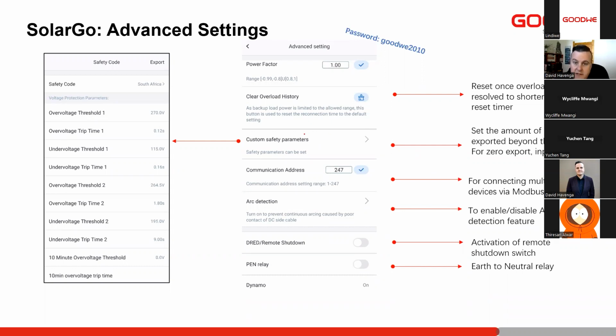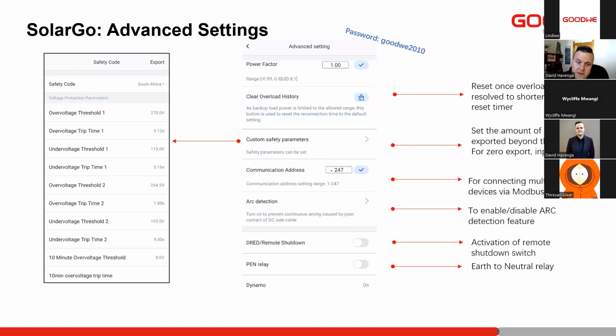Next, we have custom safety parameters. If you do select a country safety parameter, but you have special requirements, you are welcome to also adjust this. If you have a country that has very specific requirements for the inverter connection, you can adjust these values individually. Next is the communication address. The communication address is only really used when we are paralleling or connecting to EMS devices or third-party devices. Then we can change the communication address for the RS485 bus.